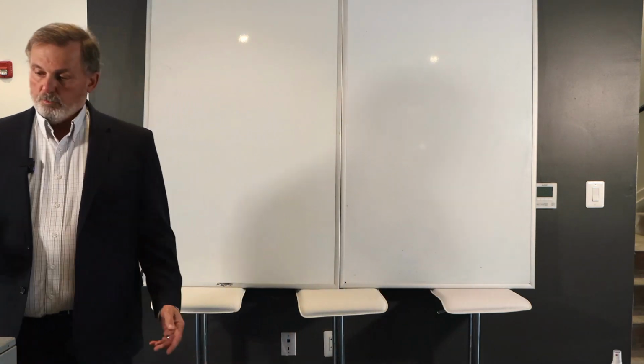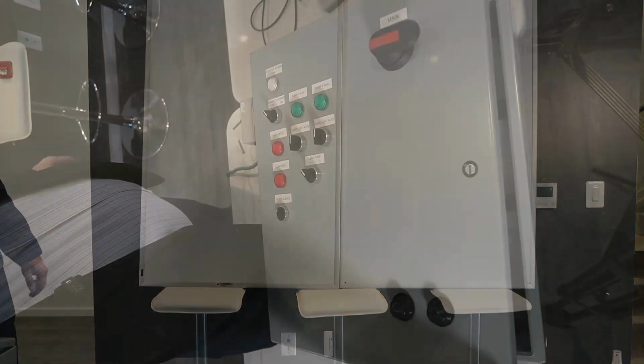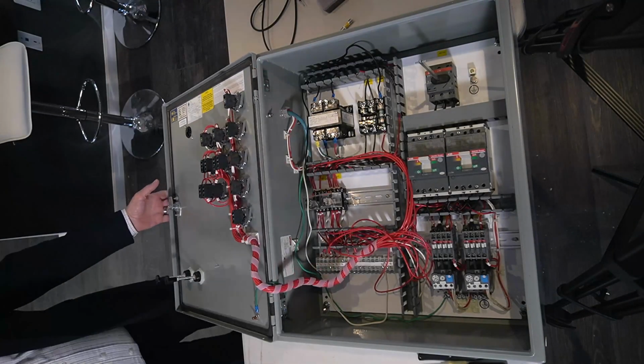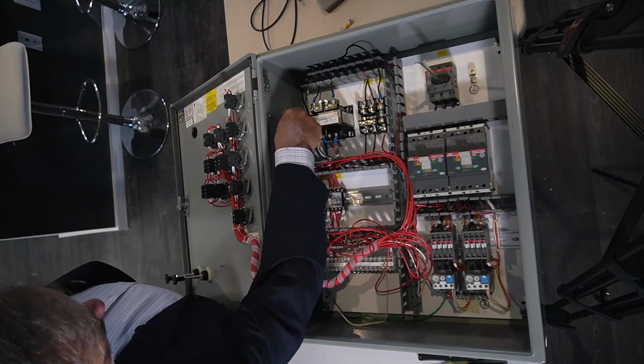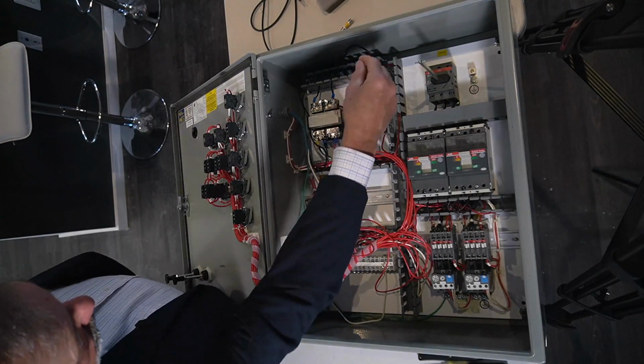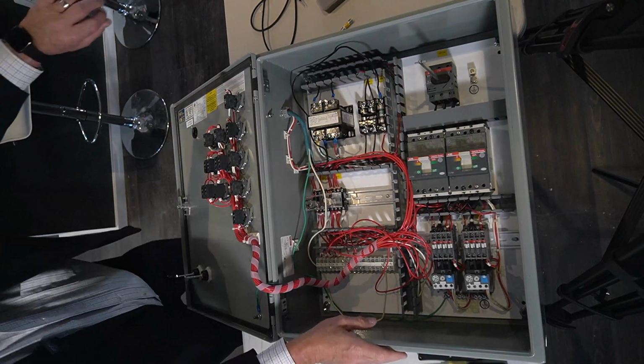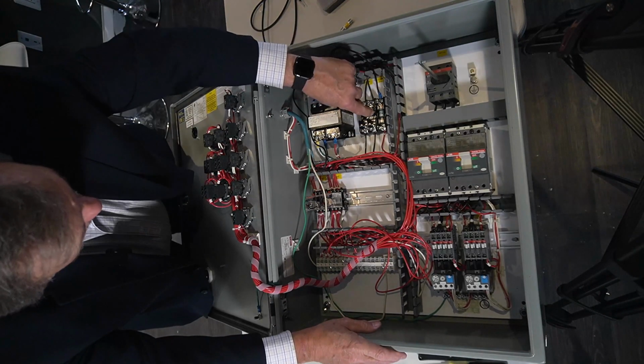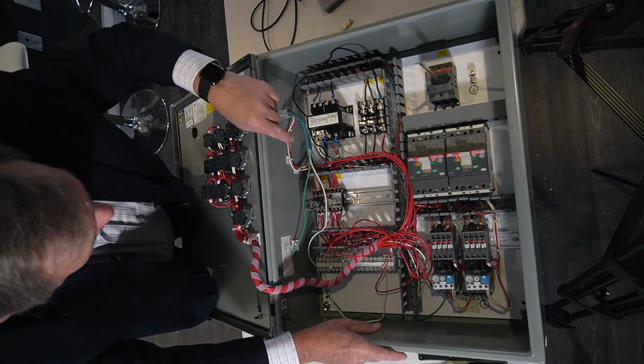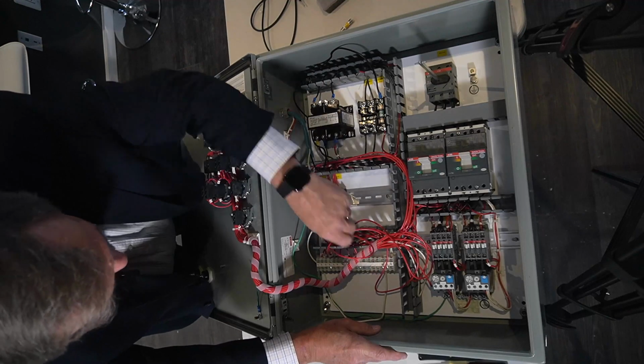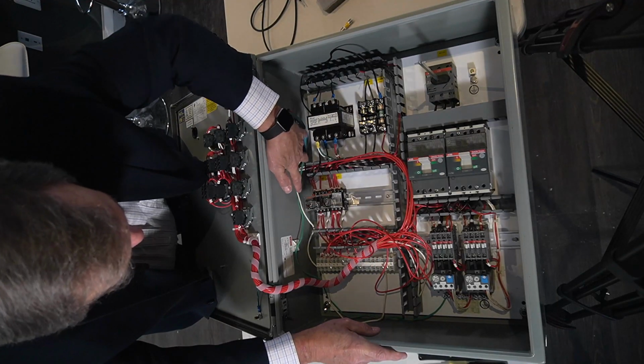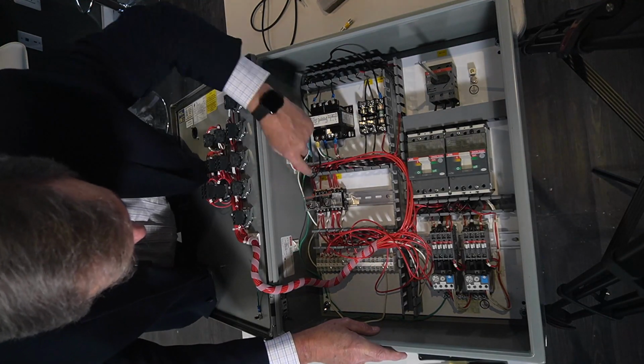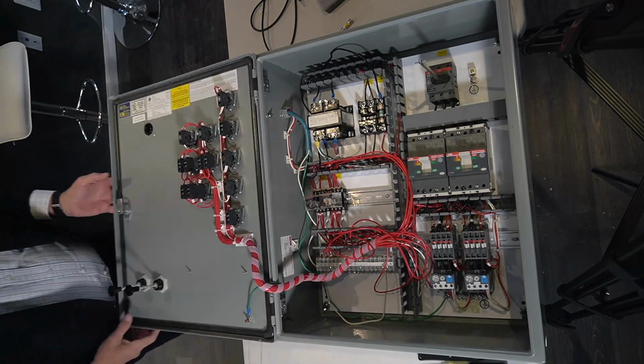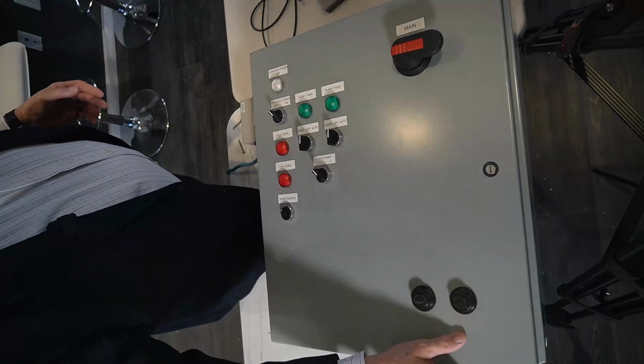Okay, moving right along, now that we've got the transformer figured out, what I've done is I've wired the control power into the control circuit. This is my hot coming off my extension cord. I'm going to keep the fuse in the circuit. The neutral is tied into the neutral bus on the control side. And of course, I'm keeping the frame grounded. Always want to be safe. So let's take a look at our basic function.